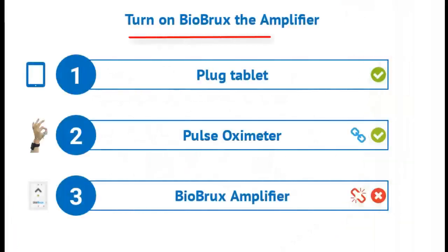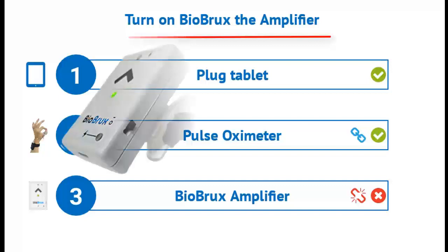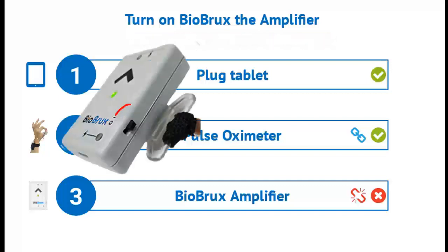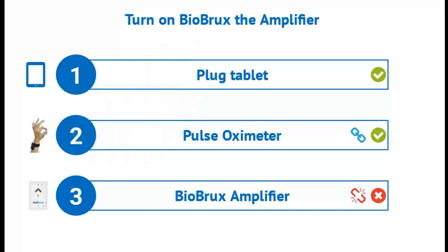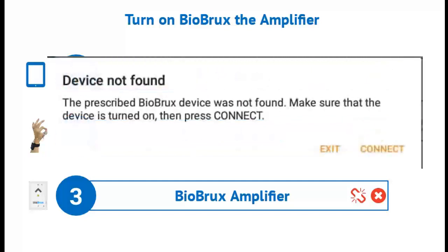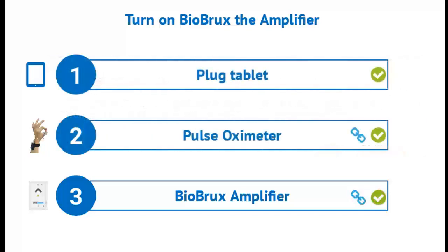Next, the tablet will prompt you to power up the BioBrux amplifier. To turn on the BioBrux amplifier, move the small black switch to the up position. To indicate that the BioBrux amplifier is on, there will be a green blinking light located in the center of the amp. Once the BioBrux amplifier is detected, the tablet will advance to the next screen. Once the screen advances, the blinking green light will automatically be turned off, but the amplifier will remain on. If the BioBrux amp was not detected, a dialog box will appear indicating to connect. Tap Connect. This will connect the BioBrux amplifier to the application.